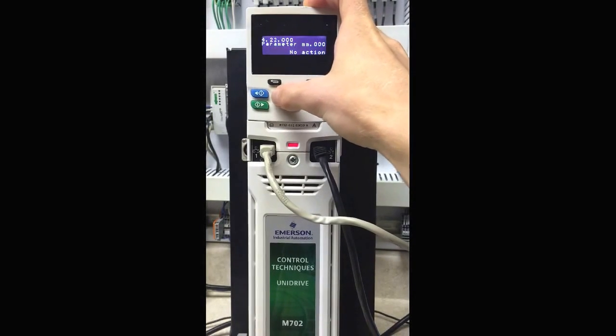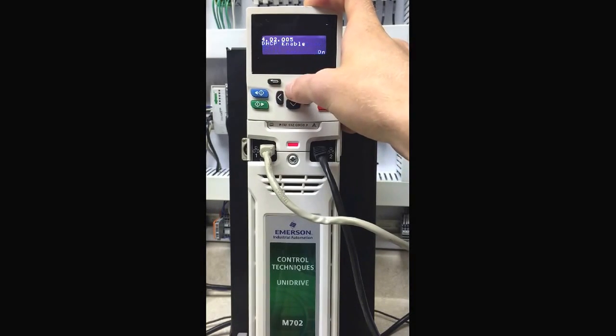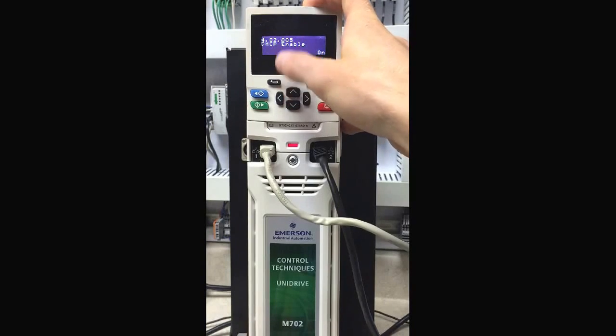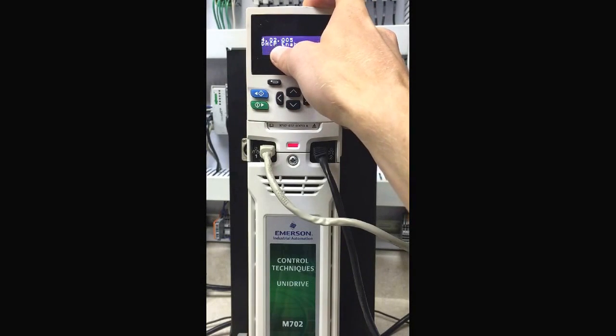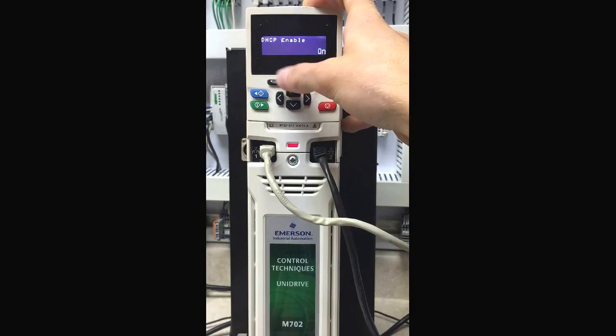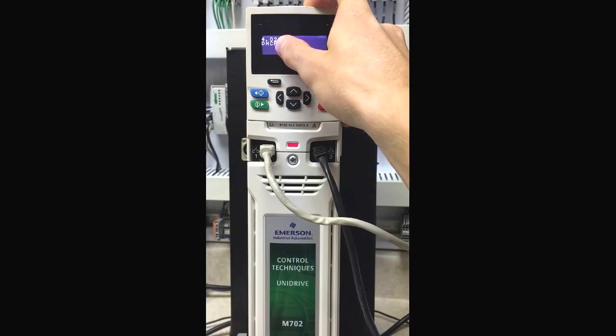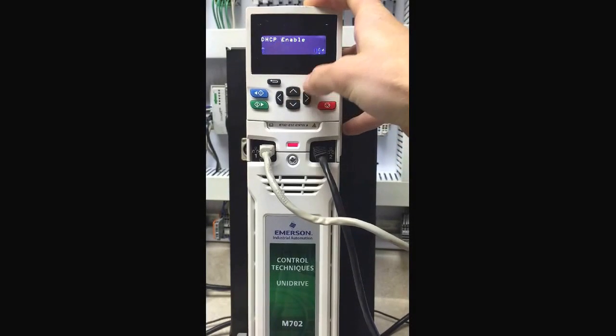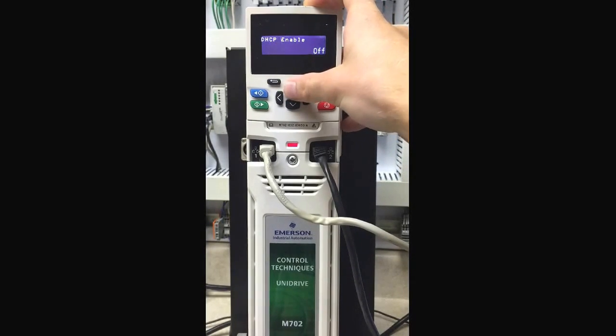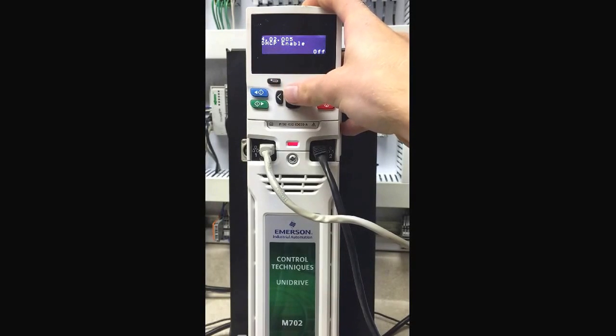Next, we will go to the slot 4 menu to set up the IP address so that way we can communicate using the Unidrive M-Connect software. First, we will want to disable the DHCP. So this is slot 4, menu 2, parameter 5, and we'll turn this to off. This will allow us to set a static IP address for the drive.